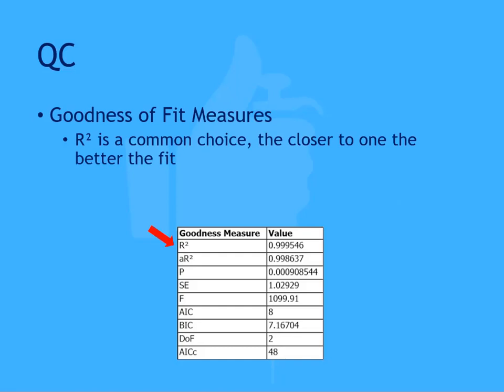Next, select a goodness of fit measure that you will use as your standard for assay validation. R-squared is a relatively simple goodness measure where the closer the value is to 1, the better the fit. You could define an acceptable limit. For example, the R-squared value must be greater than 0.985.